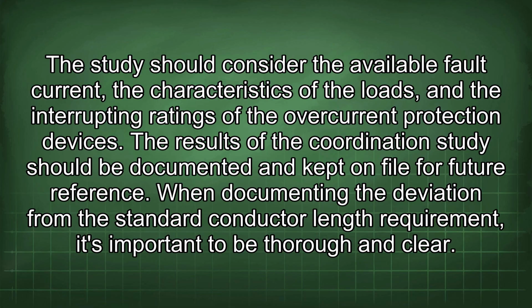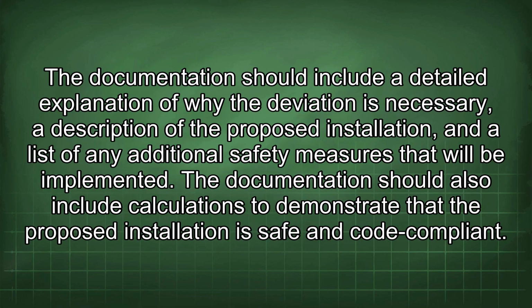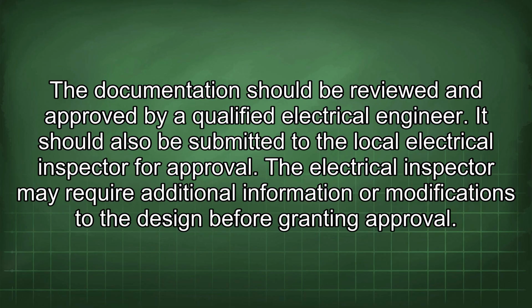When documenting the deviation from the standard conductor length requirement, it's important to be thorough and clear. The documentation should include a detailed explanation of why the deviation is necessary, a description of the proposed installation, and a list of any additional safety measures that will be implemented. The documentation should also include calculations to demonstrate that the proposed installation is safe and code compliant. The documentation should be reviewed and approved by a qualified electrical engineer.